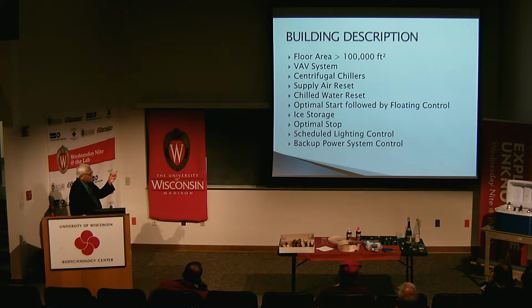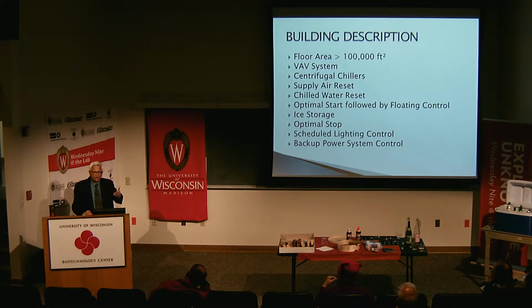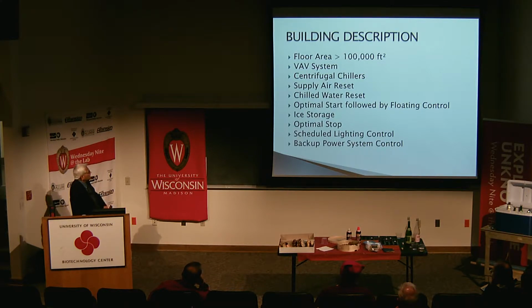And then I'm considering a control strategy called supply air reset, which is nothing but this: if the air is leaving the cooling coil, just like in your homes, then the discharge temperature can be reset to a higher temperature if none of the occupied zones call for full cooling. So there is not full demand on the cooling coil, and you can raise the temperature. So that's called supply air reset.